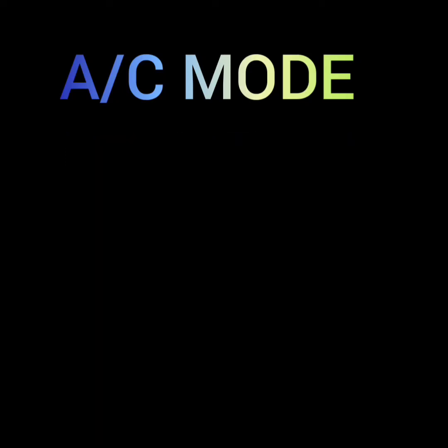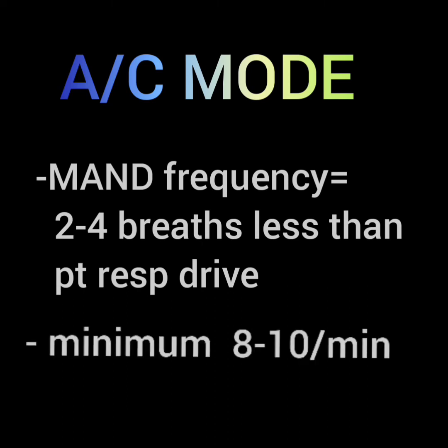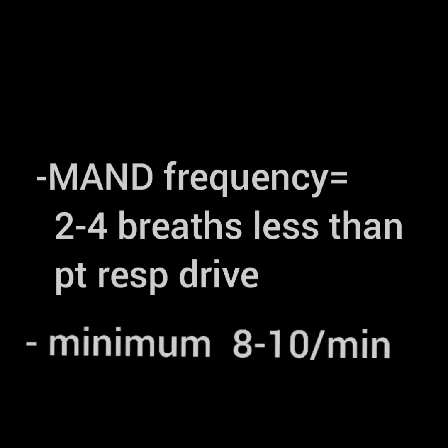And if the patient is apneic, what will happen? To counter that, a mandatory breath frequency of at least 2 to 4 breaths per minute less than the patient's assist frequency should be kept, or approximately a minimum control frequency of 8 to 10 should be kept.